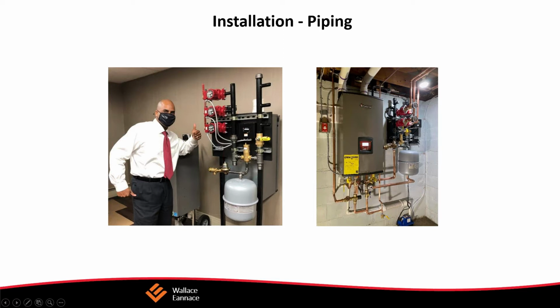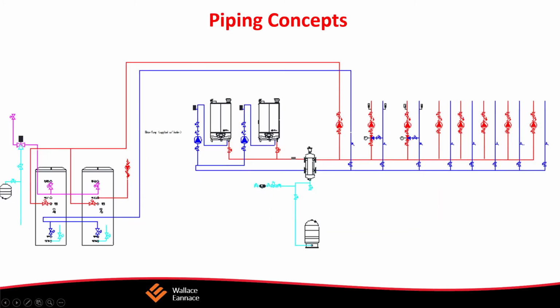One is a one pipe series loop. It uses less pipe, so it's less expensive. You can't zone without a bypass. It has larger delta T's. And one of the problems that you usually have to compensate for is that radiators at the end of the loop are going to get a much lower water temperature than those at the beginning of the loop.